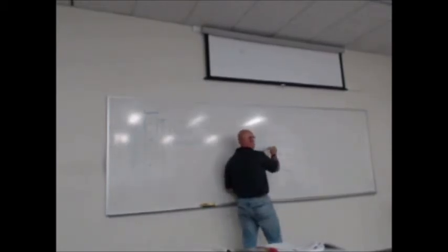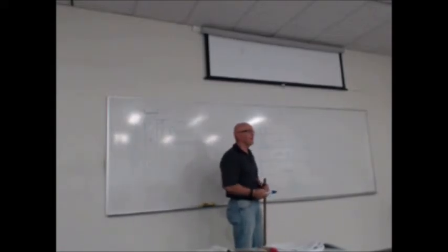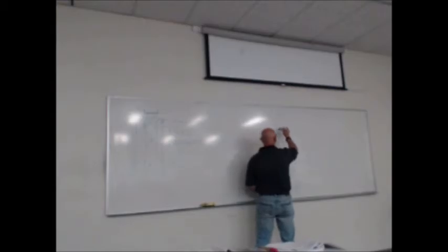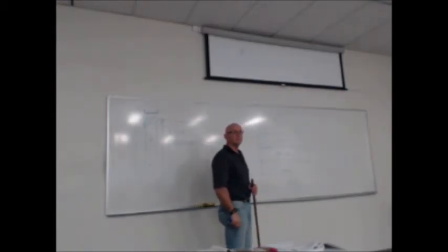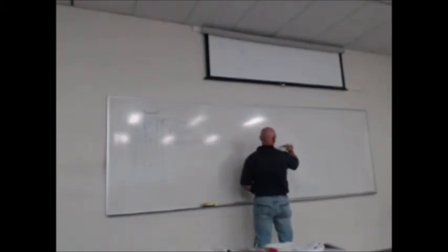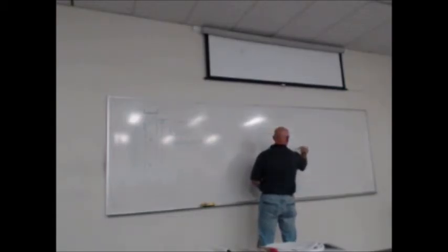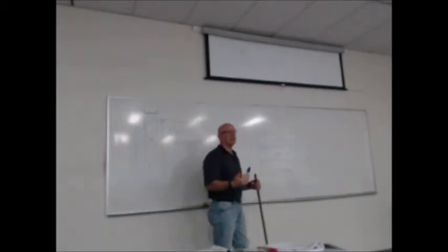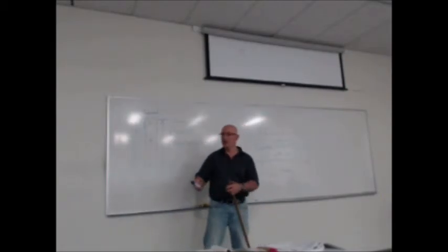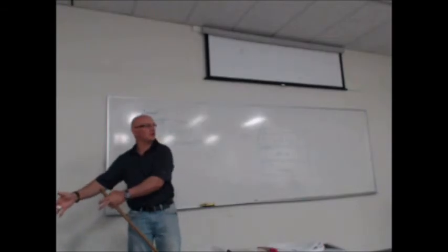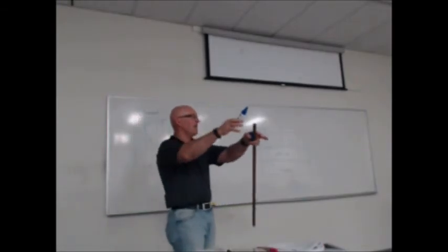How big is this thing going to go? So, would you not try and get it more central? Yeah. So when you come down, you can go that way, and then you start splitting off. You want to try and get it central, yeah? Otherwise, you're getting all your heat coming out the first few ducts, and by the time you get to the other end, you're getting nothing.